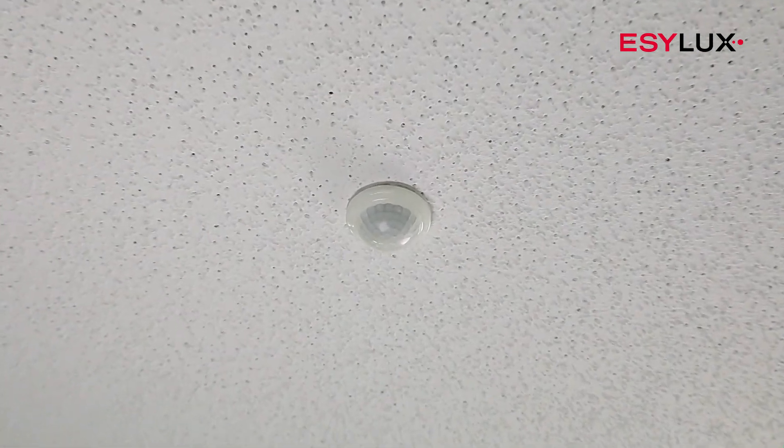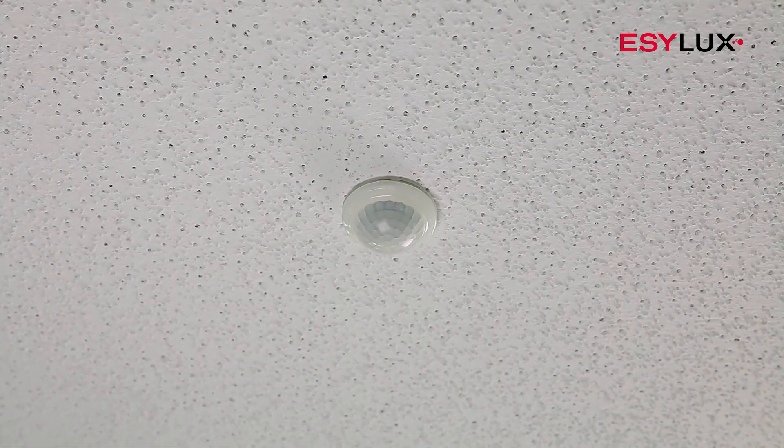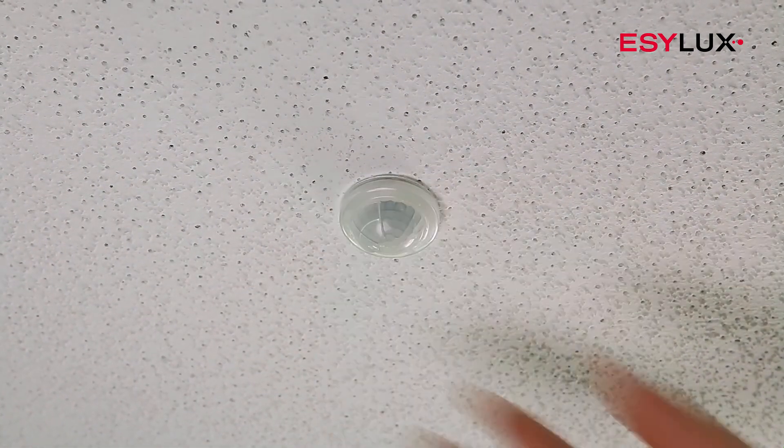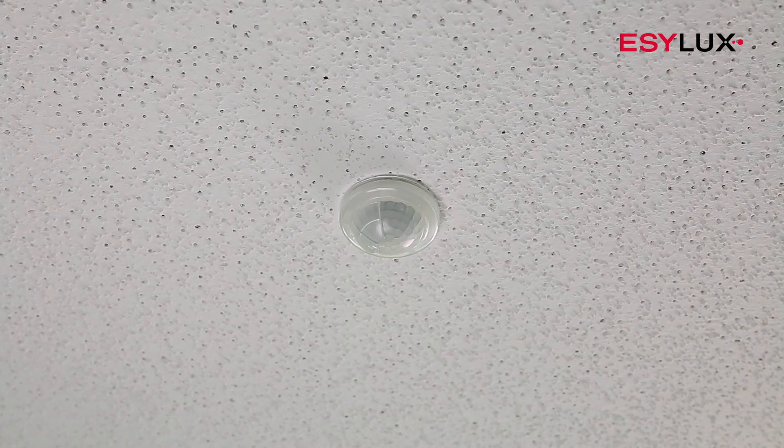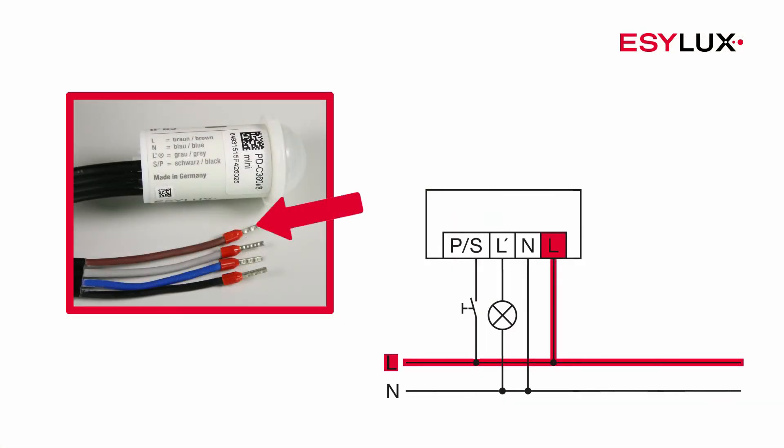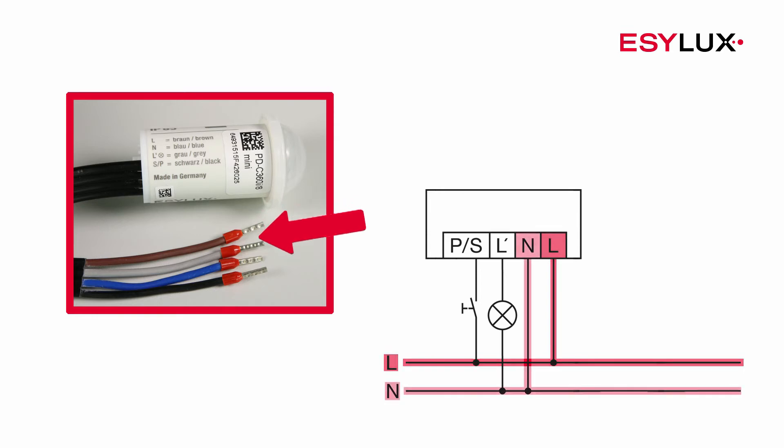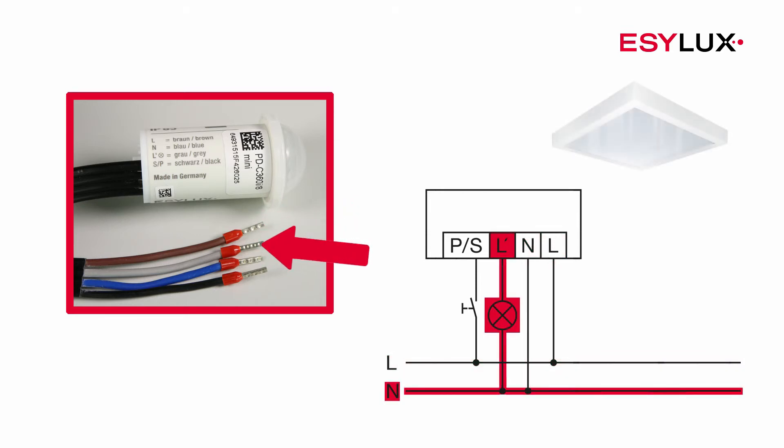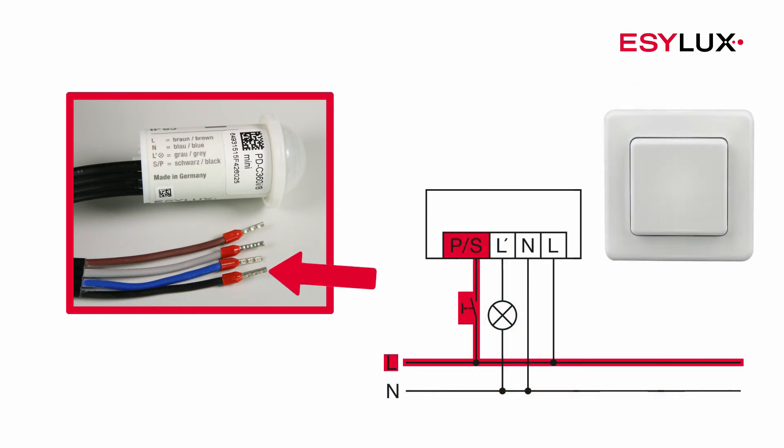The operating voltage of the detector is 230 volts AC. Connect the cables in accordance with the terminal markings and the circuit diagram. Up to 10 slave devices can be connected to expand the field of detection.